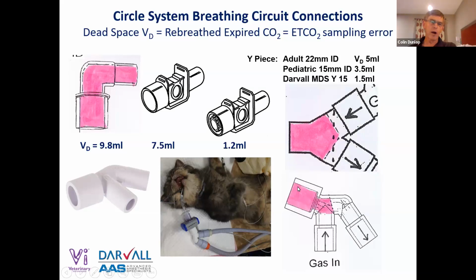So if I use that Y piece and that adapter, I've got a total machine dead space of about 2.7 to 3 mils, which for this cat's probably okay. Whereas if I put this cat on an adult Y piece, I've got 5 mils with a 7.5 mil connector, that's 12.5. And if I added an elbow connector, I've almost added 10 more mils. So dead space matters, particularly in animals under about 5 kilos.